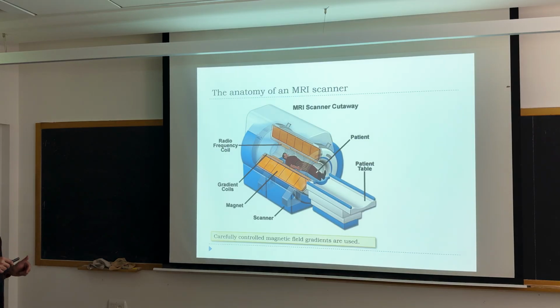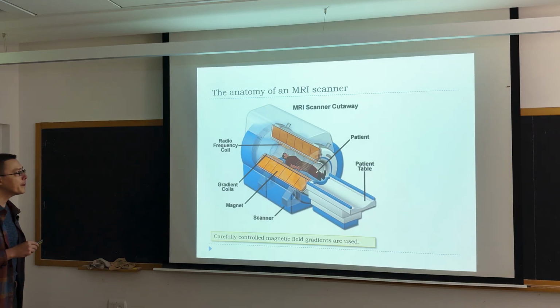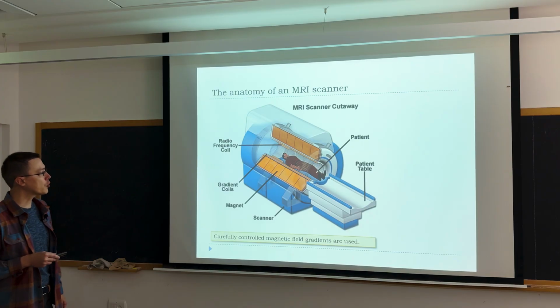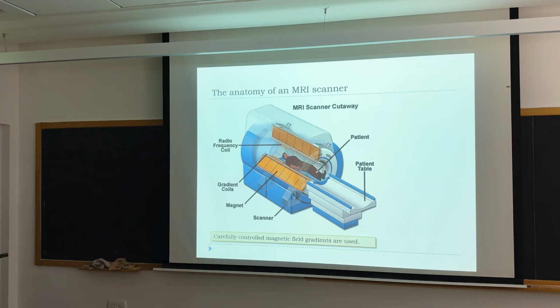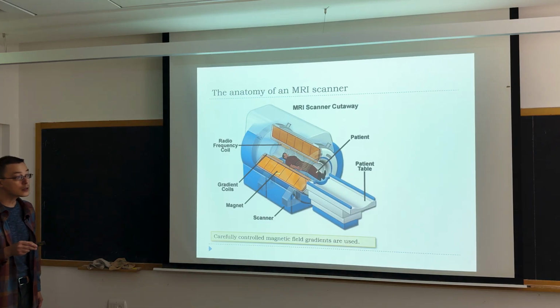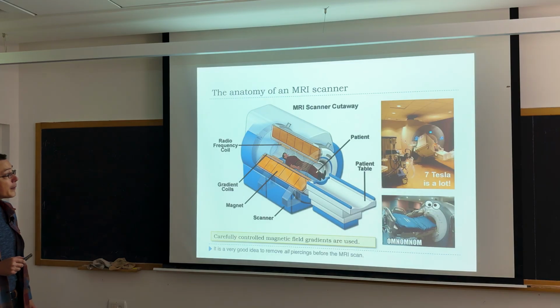An MRI instrument is a scaled up version of that, again a superconducting magnet but with a much wider bore into which you can put a patient. The coils are proportionally bigger. There are additional coils because you need to make this magnetic field non-uniform to get location dependent magnetic resonance to get your image. Well, a 7 Tesla MRI instrument is a dangerous beast.